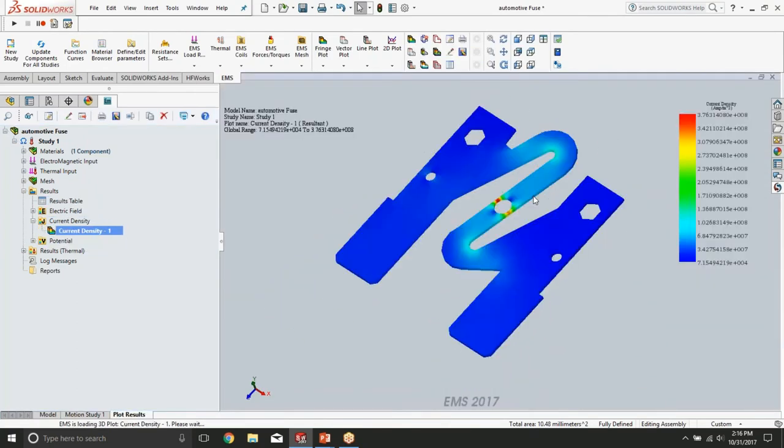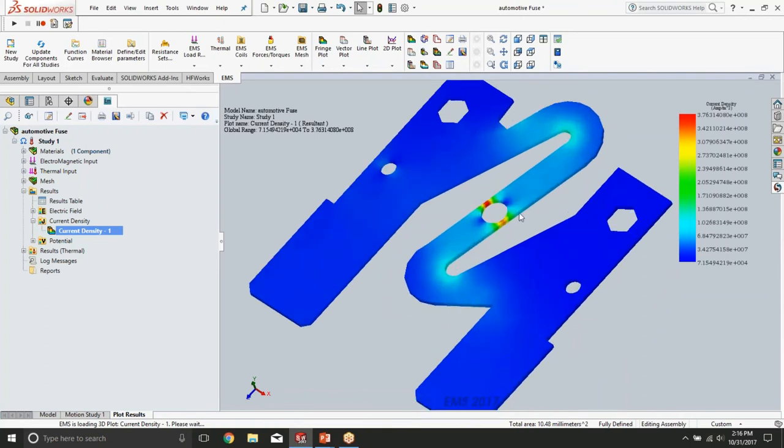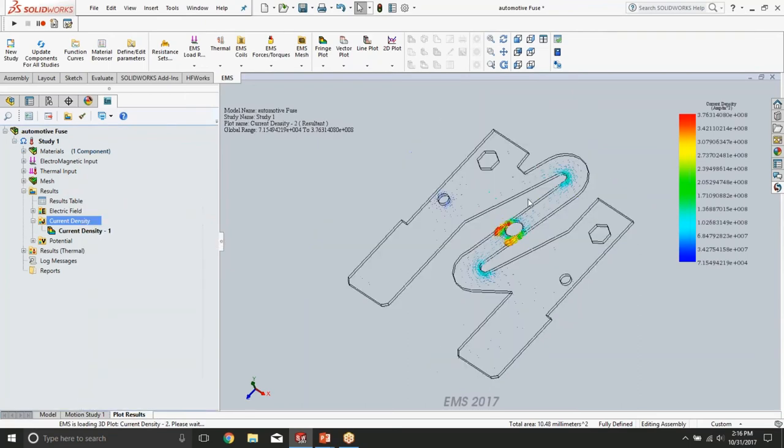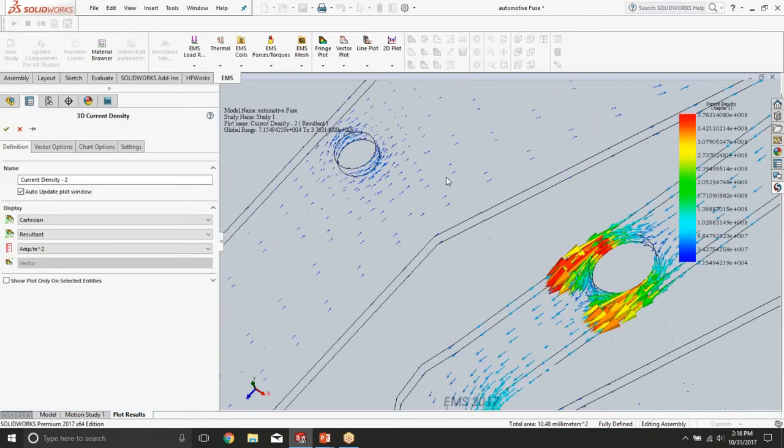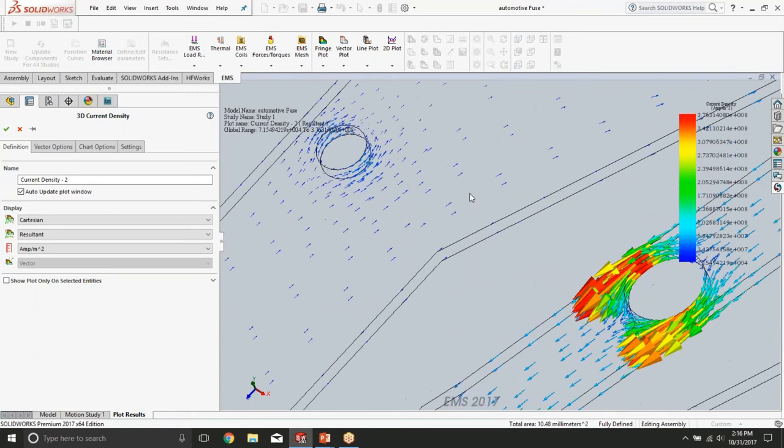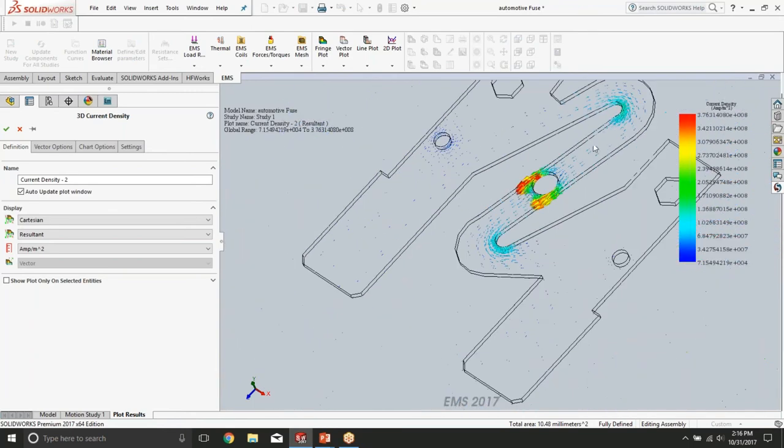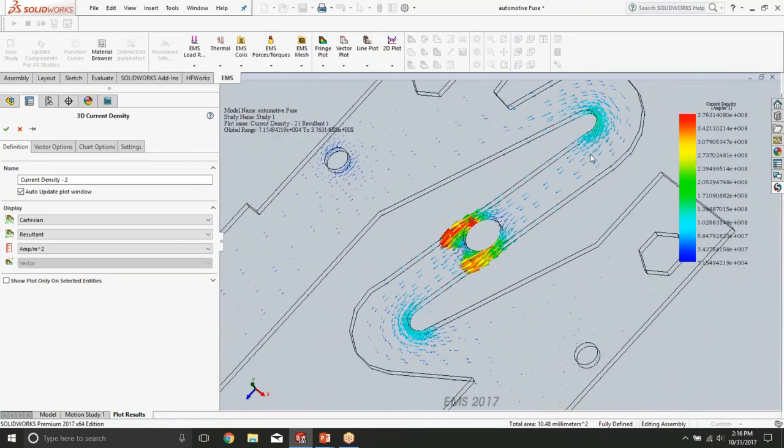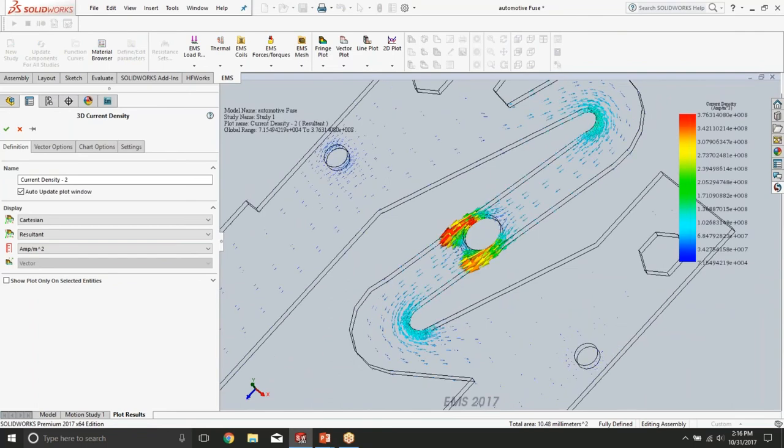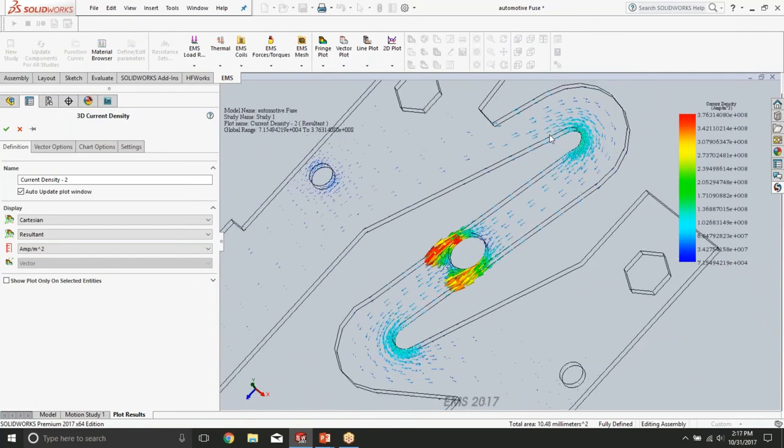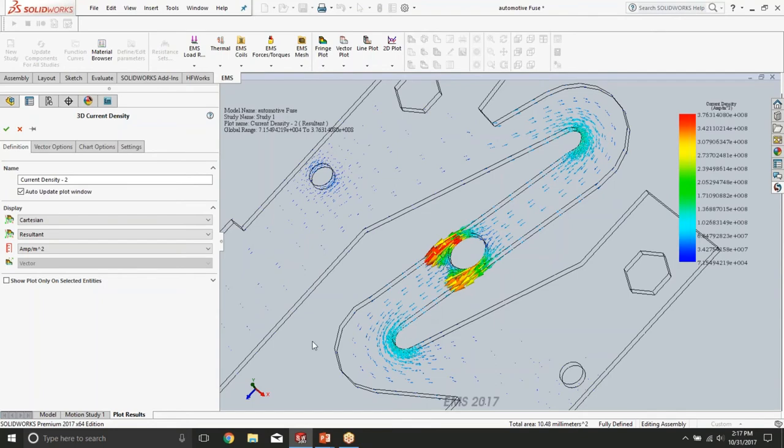Let's take a look at the current density. As expected, it is highest at this central area of the fuse bridge. Maybe we can plot as well the vector plot so that it becomes easier for you to see the direction of current flow. As we have predicted, it does reach the highest values here in these regions about the mounting holes at the center of the bridge and that curvature of the bridge.